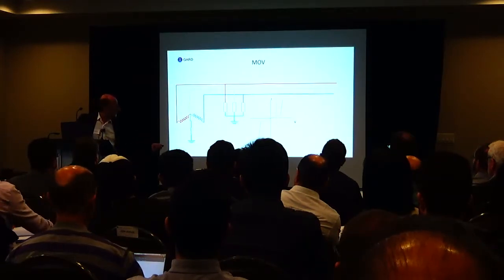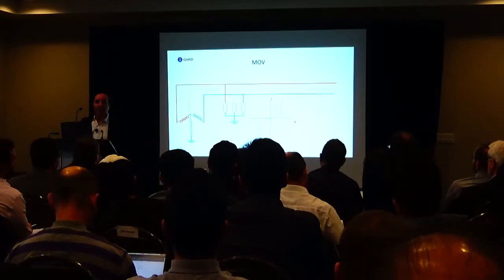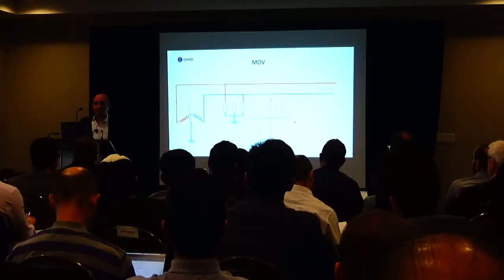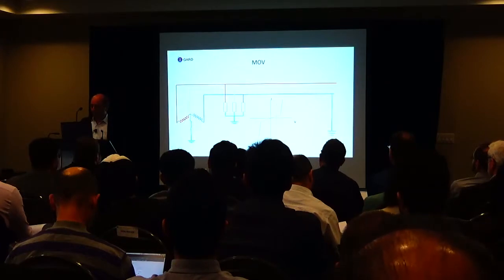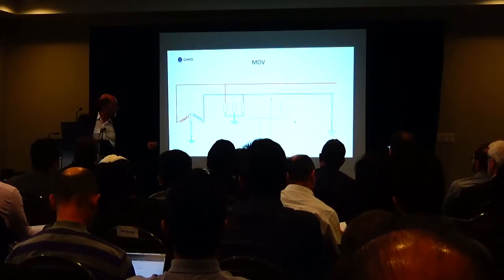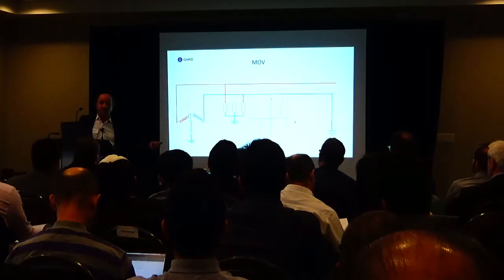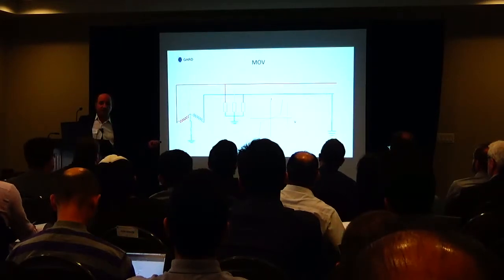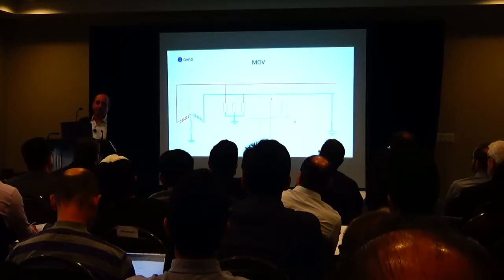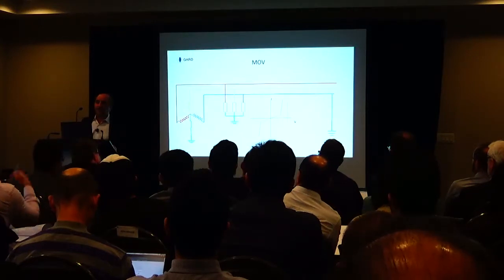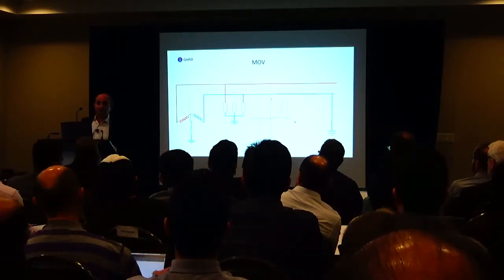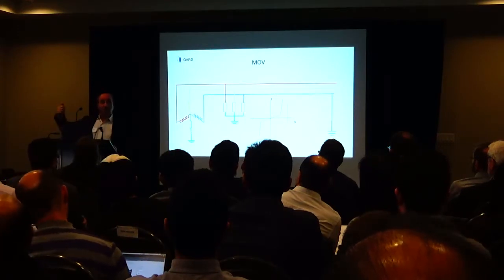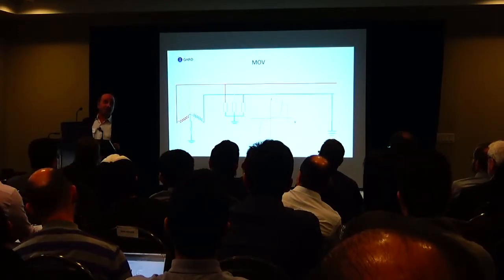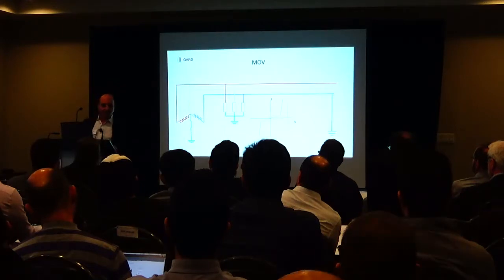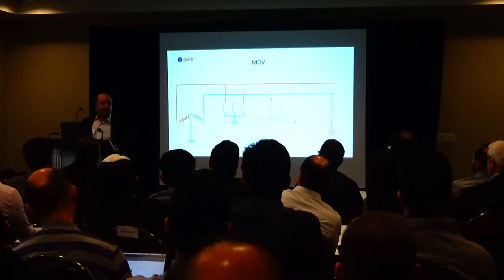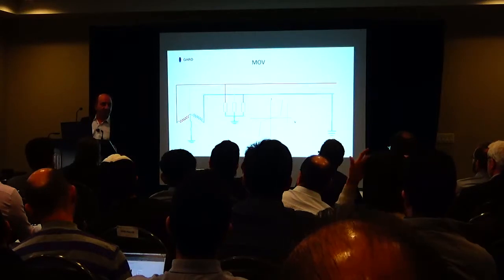So when voltage to ground is normal, you measure 347 volts to ground, everything's okay. When you get a ground fault, we now shift the two unfaulted phases to full line-to-line potential. Now we're not inside the operating range of the MOV anymore, and what happens? You get a three-phase short. One phase is already faulted, the other two are at 600 volts to ground, and you get a three-phase short. And if that happens to several VFDs or several SPDs, you have a big problem.